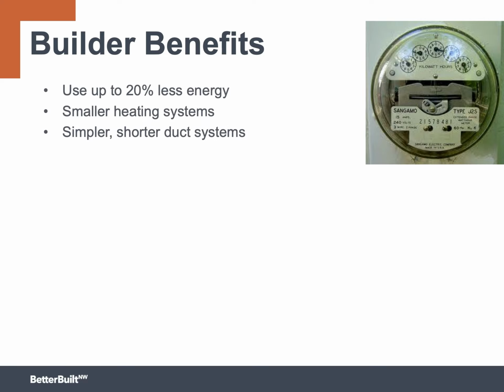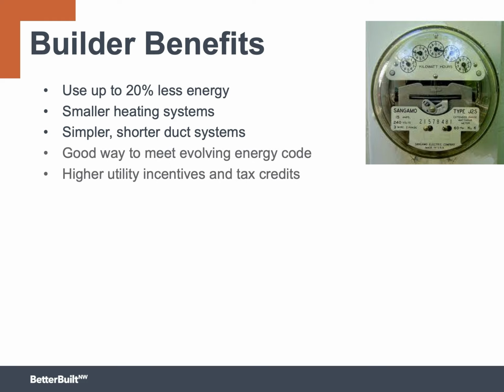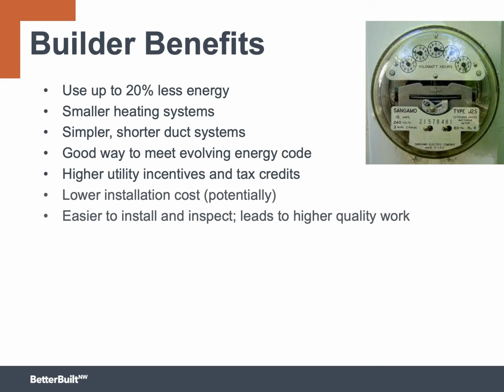Energy use can be up to 20% lower. You can have smaller heating systems, smaller equipment, and smaller duct systems too. It's a good way to meet evolving energy codes. Both the energy codes and the voluntary certification and rating programs are going to recognize ducts inside as a significant energy savings. There may be higher tax incentives or utility incentives. There will very likely be less cost in building an HVAC system that's smaller and shorter and lower capacity. So if you're putting in smaller equipment and shorter ducts, there should be some cost savings there. Those savings may take a while to materialize in the marketplace as trades learn how to do these measures.